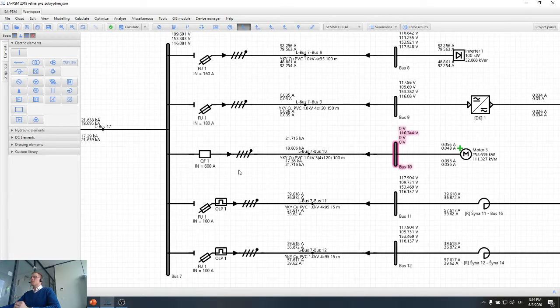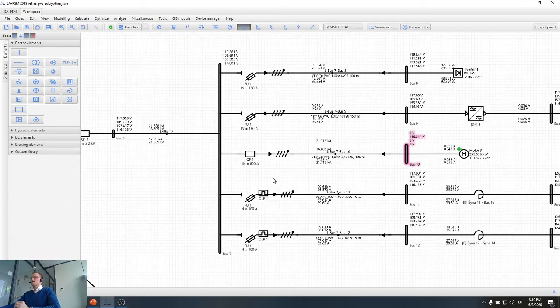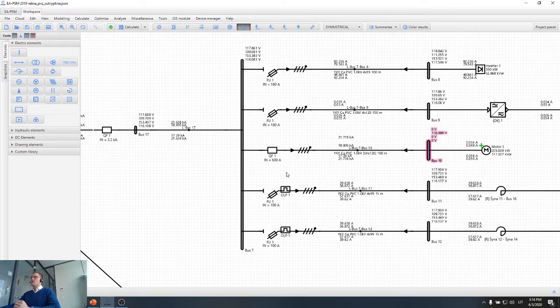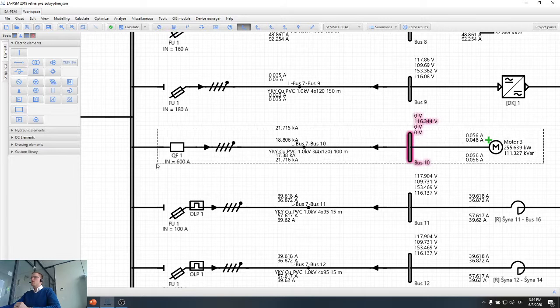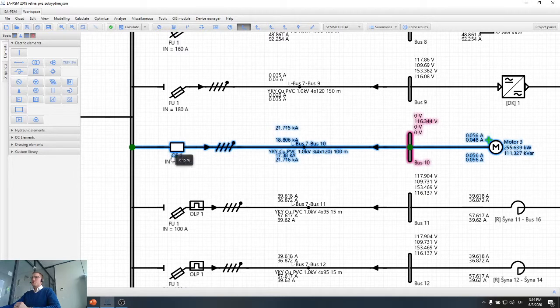The next important principle is basically reliability of the protection devices, and what this requires from us is that protection devices should have backup protection. So we can see that, for example, this cable and this motor are protected by the circuit breaker here, again 600 amps. However, if this circuit breaker for any reason won't work, so maybe some failure of the breaker, maybe someone instead of the breaker put just a metal bar and connected the bus bars, so the breaker does not exist. So there should be another breaker which will trip in case of the short circuit.